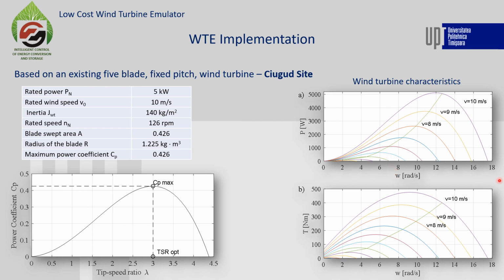Among the characteristics, this shows the load curve implemented in the inverter. The load curve depends on the DC voltage, but since it's a permanent magnet synchronous generator, the DC voltage depends on the angular speed. The curve implemented in the inverter is slightly deviated from the maximum power point of some characteristics, in order to obtain an optimal overall regime, since the curve was implemented as a 4-degree polynomial.